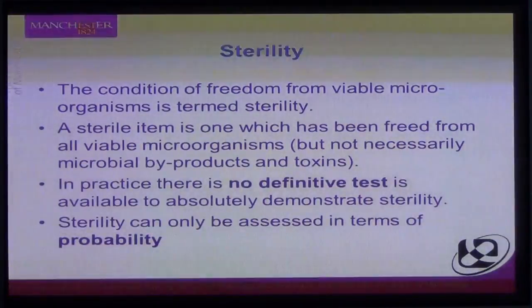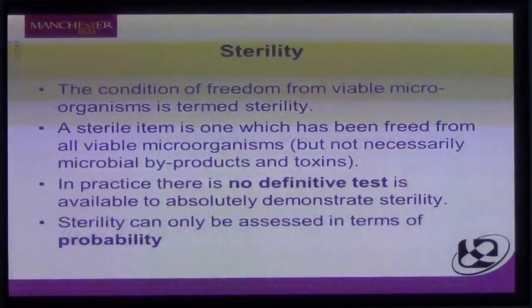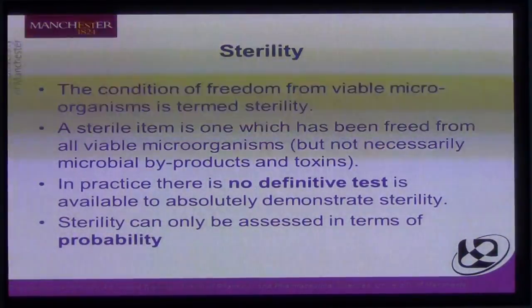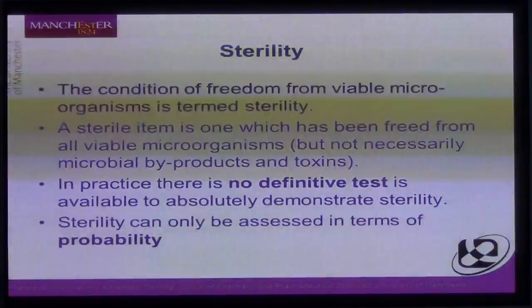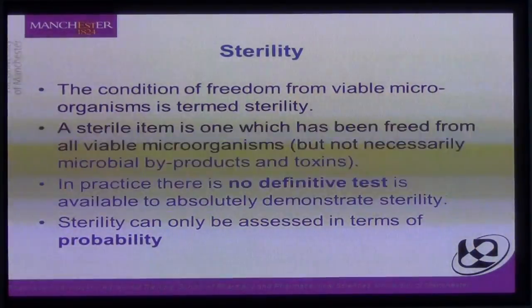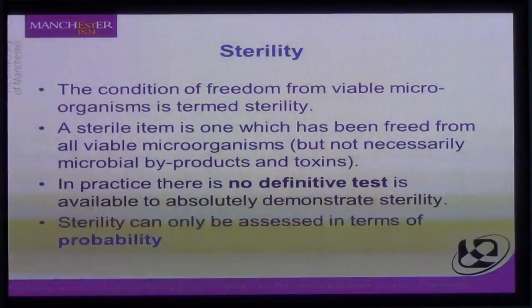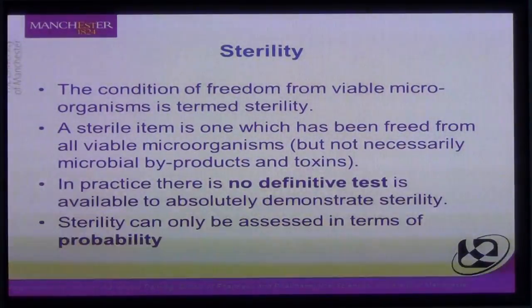In practice, there is no definitive test to demonstrate absolute sterility. We cannot prove sterility with current technological limitations. We can only talk about something being sterile in terms of probability. We can give ourselves a comfort factor that there might only be a one in a million chance that something is not sterile.